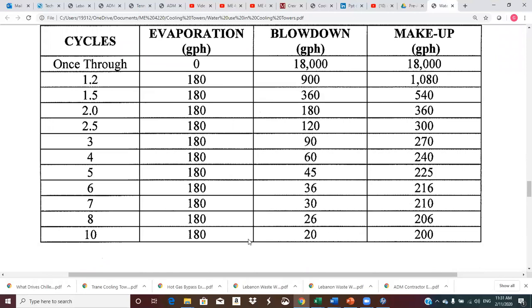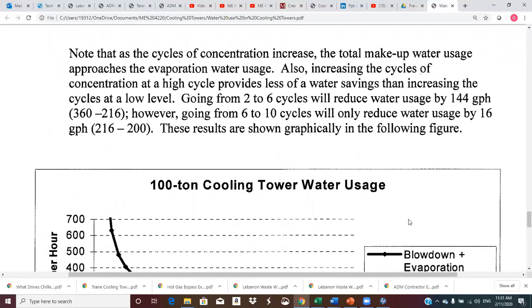And so you see, if we can run more cycles, which is less blowdown, you see the blowdown flow going down. This would be the cycles. Then you see the makeup water goes way down. And we accomplish that by doing better cleanup on the water that's introduced to the tower. Note that as cycles of concentration increase, total makeup water usage approaches the evaporation. Also, increasing cycles of concentration at higher cycles gives less water savings.